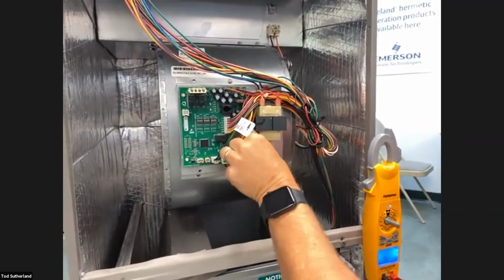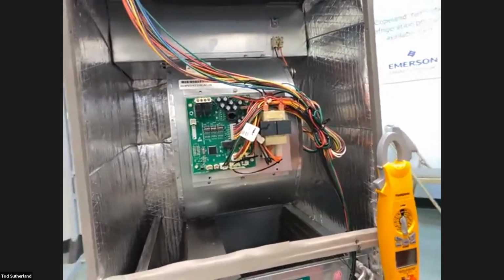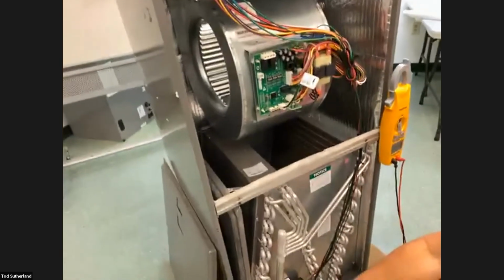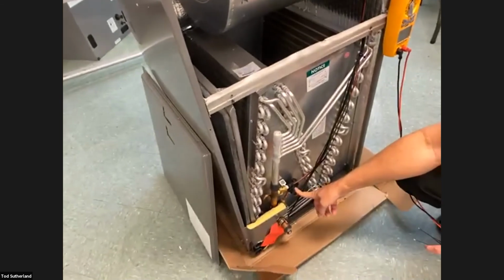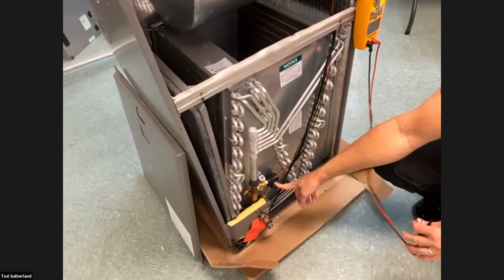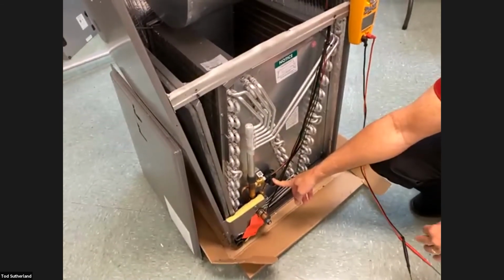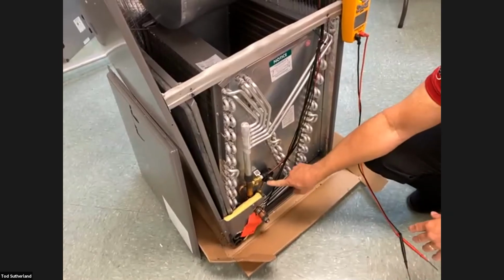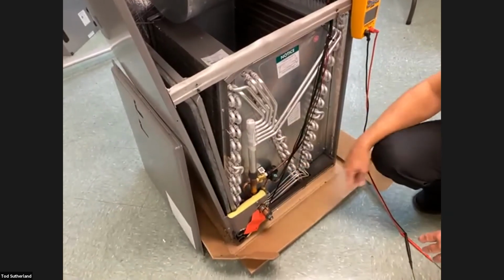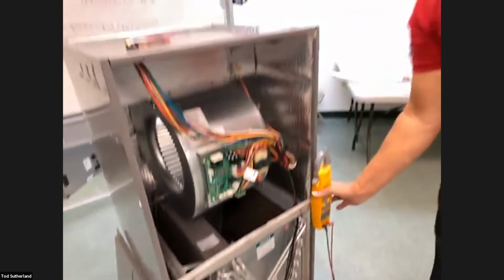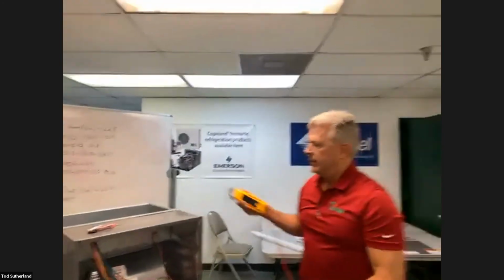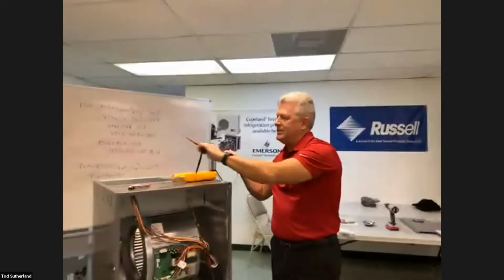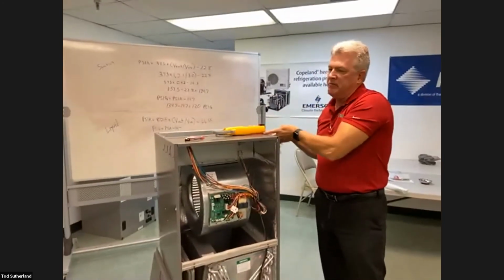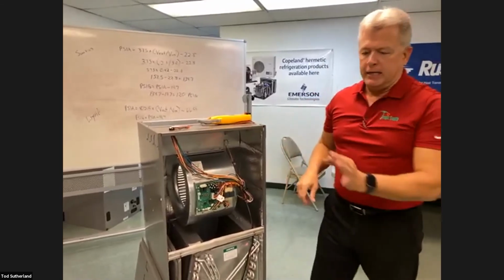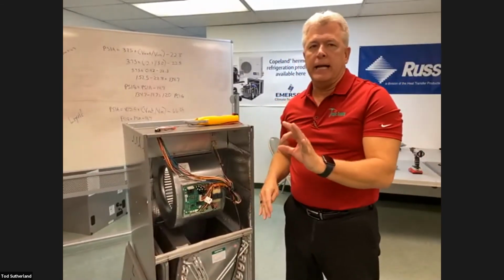And again, shutting power off to the unit, turning power back onto the unit, you should hear this stepper motor clicking. Okay, there are ways that you can force these valves open or closed. You can pop these stepper motors off of there. There's a couple of companies out there that make EEV magnets. They're usually in 2 different sizes that cover almost every manufacturer and almost every valve. And it's basically a round magnet.